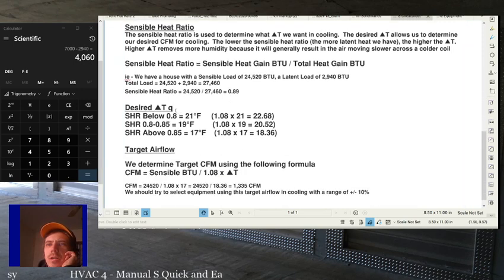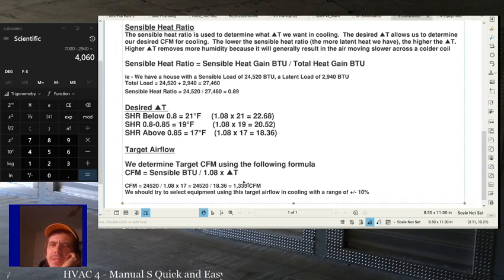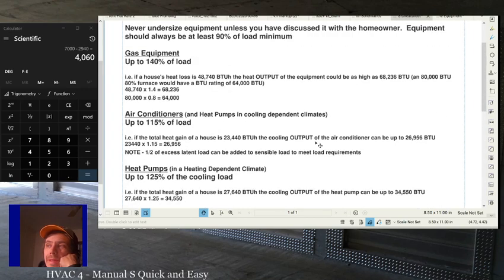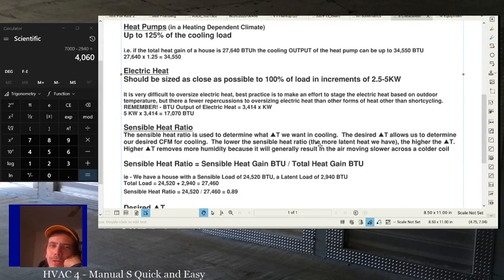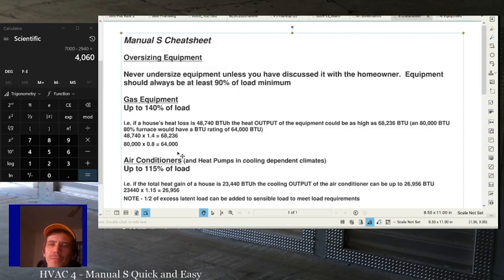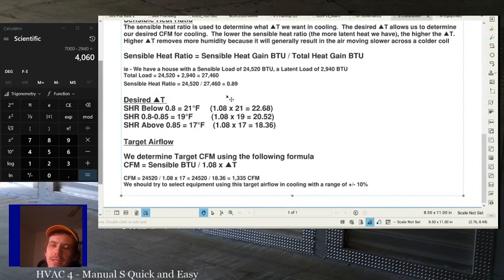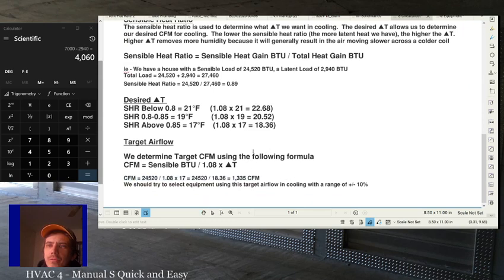But just remember that your sensible and your latent, the equipment has to be able to meet those numbers independently. If the total's right, it doesn't mean that the equipment is properly sized. The equipment has to be properly sized and have enough sensible and latent heat available to work. Okay? And that is most of what Manual S is about. Those are the most important points out of Manual S, to make sure that you're not oversizing or undersizing equipment. So, with that in mind, let's take these numbers we had down here for this target airflow and our load, right?